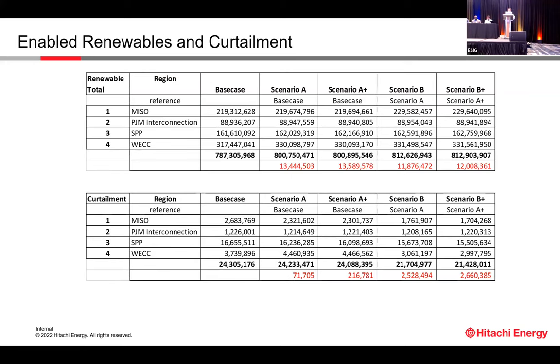Another thing I want to point out is that it enables renewable development. You can see the top chart refers to the increase of renewables in the system, and the bottom is the reduced curtailment. In scenario B, we installed nine terawatt hours of new renewables. In the end, scenario B almost increased renewable generation by 12 terawatt hours because they reduced the curtailment by 2.5 terawatt hours. So that's the benefit this HVDC system can help with.